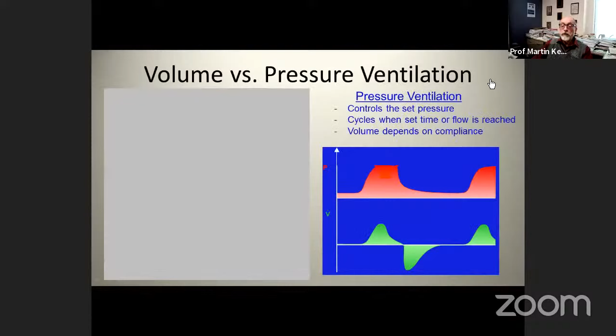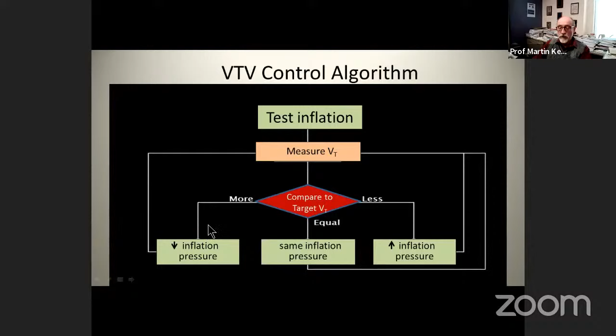The basic control algorithm is relatively straightforward. This is how volume guarantee began. There was a variety of other ways different manufacturers approached the issue, but ultimately everybody has moved to this basic algorithm, which means essentially there's an initial pressure controlled ventilator cycle. The tidal volume that results is measured and compared to the target tidal volume that you set. Then, if the tidal volume measured is less than target, inflation pressure will go up. If it's equal or within a few percentage points, there will be no change. And if it's above target, inflation pressure will be lowered for the next cycle. So it's always looking back a little bit.